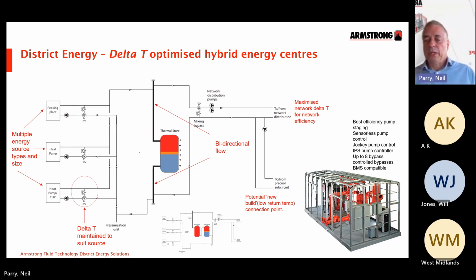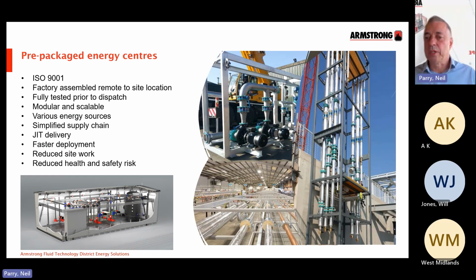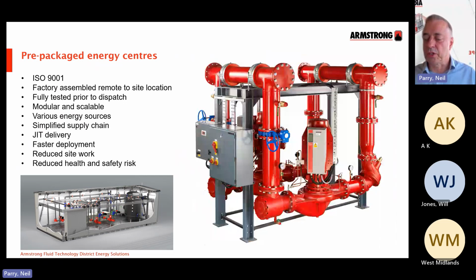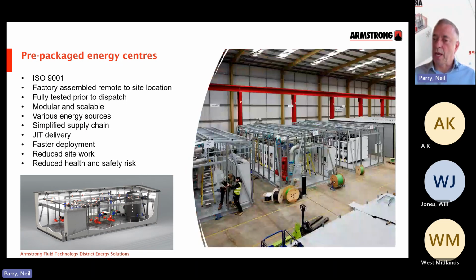So at Armstrong we have taken that arrangement and put it into a prepackaged energy center, which can have roof, walls, everything included: the thermal store, the energy sources, all the pumps, and so on. The idea is that these come off a production line in various different outputs. They are modular, so you can expand them over time as your heat network grows and has higher heat demands. Trying to assemble all of the individual components on site just delays that whole process. It's much better, and speeds up our path to net zero, to produce these on a production line approach and then fire them out to the relevant projects as and when they're needed, so they can just be slid in, connected up, and instantly commissioned and up and running. Much faster delivery of your net zero building.